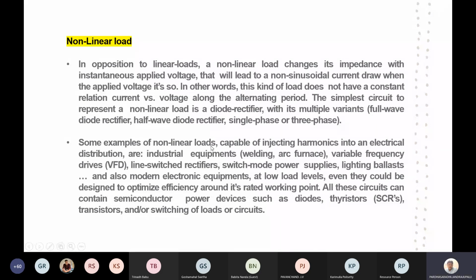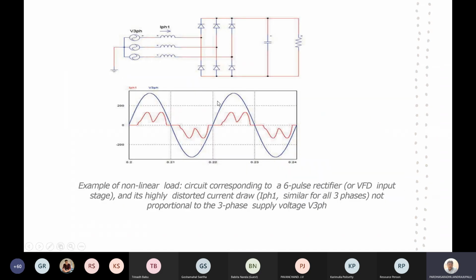nonlinear load is a diode rectifier with its multiple variants like full wave rectifier, half wave rectifier, single phase or three phase. Some examples of nonlinear loads capable of injecting harmonics into an electrical distribution or industrial system are equipment such as welding, arc furnaces, variable frequency drives, line switching rectifiers, switch mode power supplies (SMPS), lighting ballast, and also modern electronic equipment at low load level. Even they could be designed to optimize efficiency around the rated working point. All these circuits can contain semiconductor power devices such as diodes, thyristors, transistors. So the main source of harmonics is only nonlinear loads.